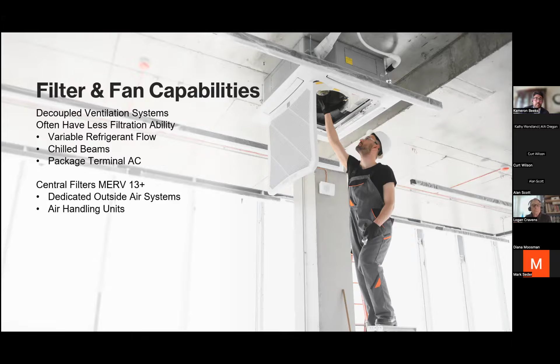Now, centralized equipment like air handling units or dedicated outside air systems, the ones that are up on the roof, those tend to have plenty of adequate pressure to handle a MERV 13 or better filter. And so what do I mean by a MERV 13 filter? MERV stands for minimum efficiency reporting value. Effectively, it's just how many of the little particles I can get out of the air. So MERV 13 is what's been recommended by ASHRAE, or MERV 13 and better.